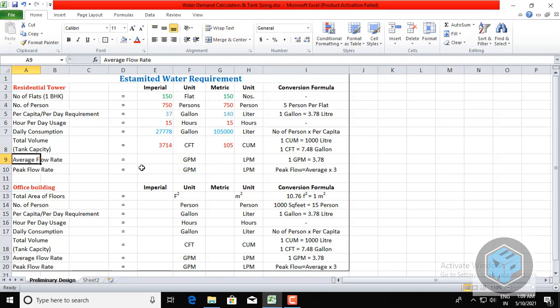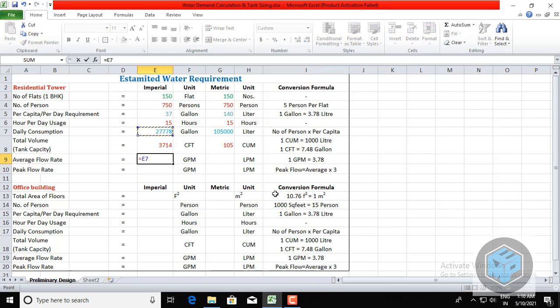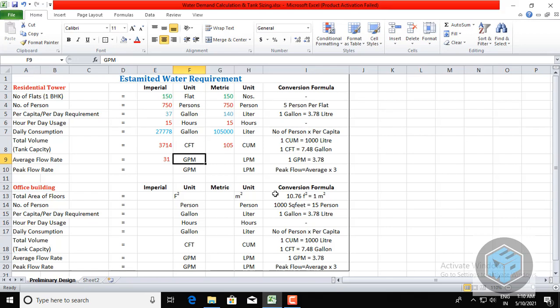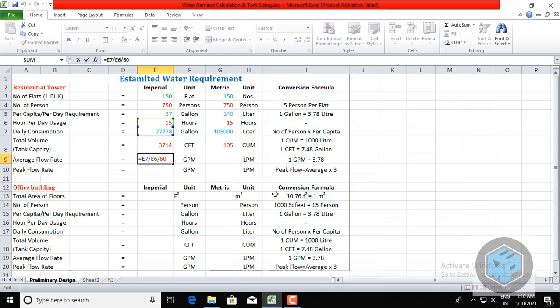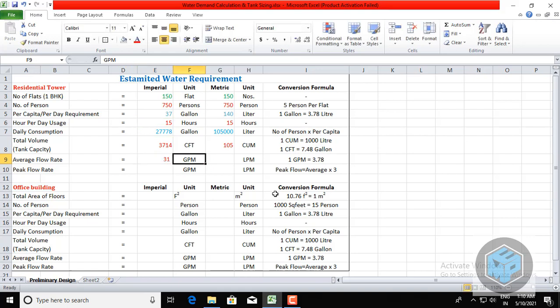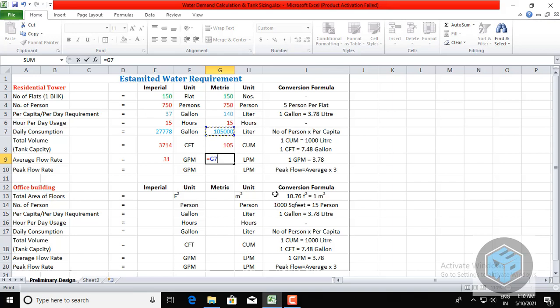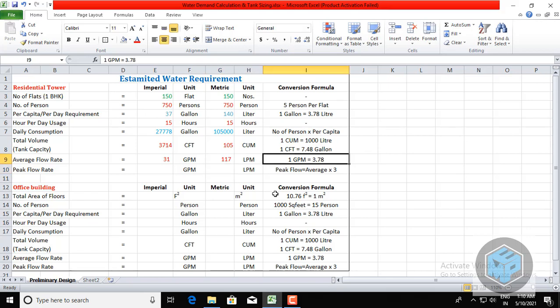Now let's calculate the average flow rate — this is the water requirement for the sump tank and underground tank. The formula is: daily consumption ÷ hours per day ÷ 60, because we want the flow rate in liters or gallons per minute. That gives 31 GPM (gallons per minute) in Imperial, and 117 liters per minute in metric. Note: 1 GPM = 3.78 liters per minute.